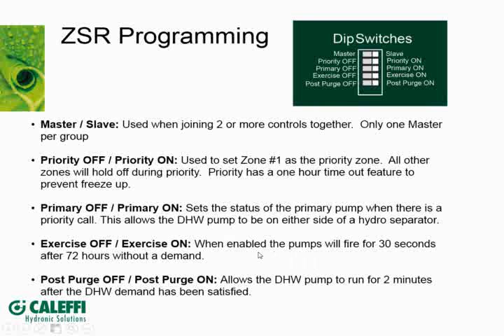Exercise on, exercise off. We talked about that a little bit. No demand for 72 hours, it'll fire for 30 seconds. Post-purge is only for the priority zone. What it will do is, after priority has been satisfied, it'll open up the domestic hot water contacts, so it'll stop firing the boiler, but it will continue to run the priority pump for 2 minutes to help purge some of that hot water out of the boiler.